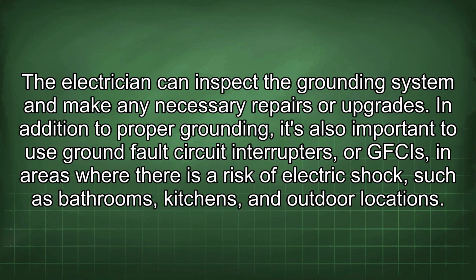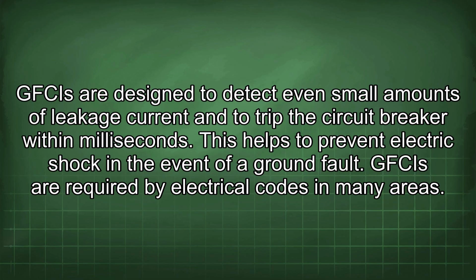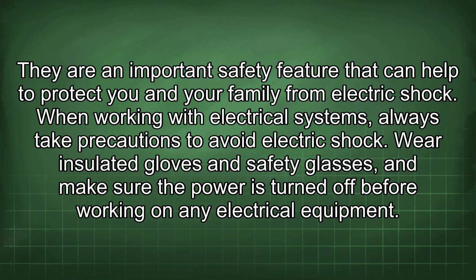In addition to proper grounding, it's also important to use ground fault circuit interrupters, or GFCIs, in areas where there is a risk of electric shock, such as bathrooms, kitchens, and outdoor locations. GFCIs are designed to detect even small amounts of leakage current and to trip the circuit breaker within milliseconds. This helps to prevent electric shock in the event of a ground fault. GFCIs are required by electrical codes in many areas. They are an important safety feature that can help to protect you and your family from electric shock.